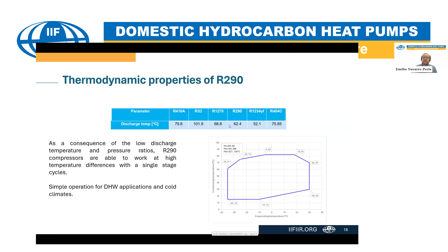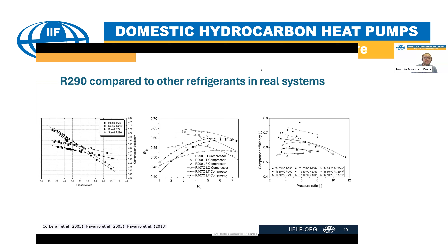First of all, I would like to comment that you can find many studies in the literature in which a compressor is tested working with propane and working with other refrigerants. And usually the most common result is that when you operate the compressor working with propane, the compressor efficiency is higher than when this compressor operates with other refrigerants. Here you can see some figures in which we have represented this kind of tests in a comparison between propane and R22, propane and R1234yf, propane and R407C.